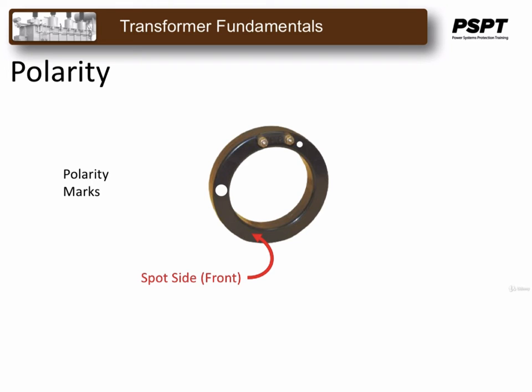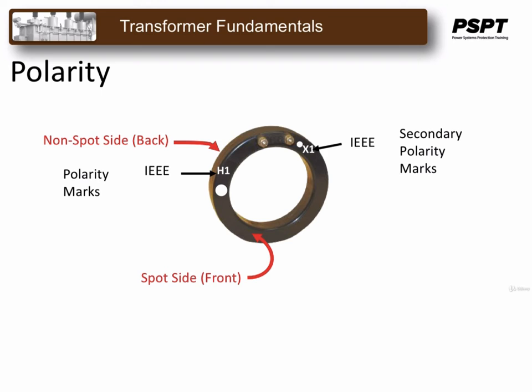In the case of a donut CT, where the primary is the conductor running through it, one side of the CT is marked with a spot. In this case, the front is spot. The back is not. The spot marks can be a dot or any similar symbol. The IEEE, the Institute of Electrical and Electronic Engineers, use H1 and X1 in place of the spots. The IEC, or the International Electrotechnical Commission, use P1 and S1.